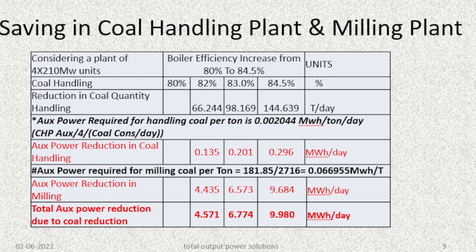Savings in coal handling plant and milling plant: if there is a saving in fuel, there will also be savings in the coal handling plant. Considering 4 x 210 MW units and a boiler efficiency increase from 80% to 84.5%, the reduction in coal quantity handled would be 144.639 tons per day. The auxiliary power required for coal handling per ton comes to around 0.002044 MWh per ton per day, giving a total auxiliary power reduction of around 0.296 MW per day.